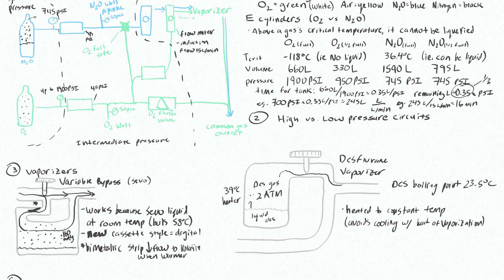Ultimately you'll have some amount of des coming out of this part, and then here's your O2 or nitrous or air mixture coming from your flow meters. They will mix and go towards the common gas outlet. This is your O2/nitrous/air from your flow meter and then onto the common gas outlet.